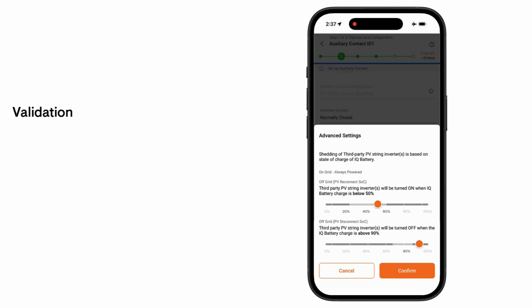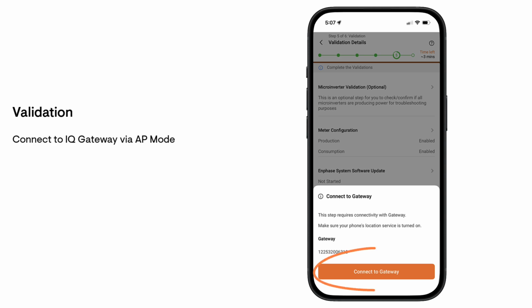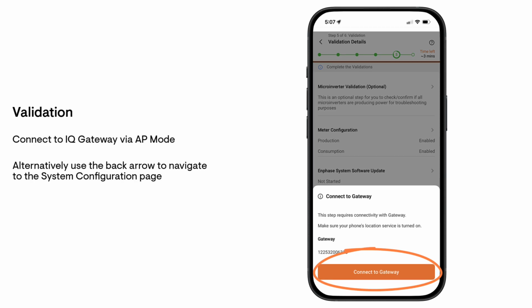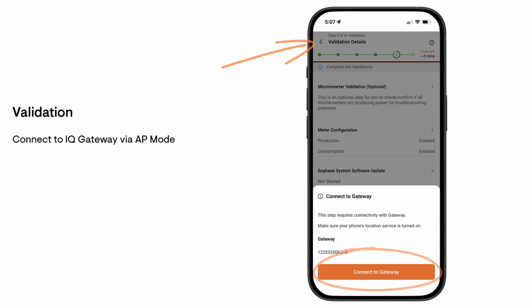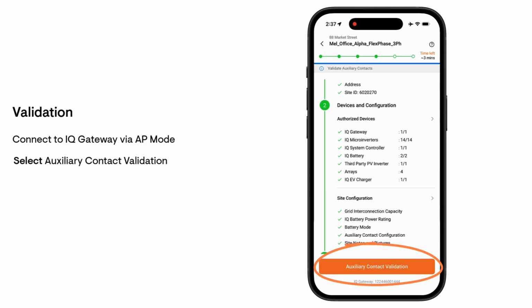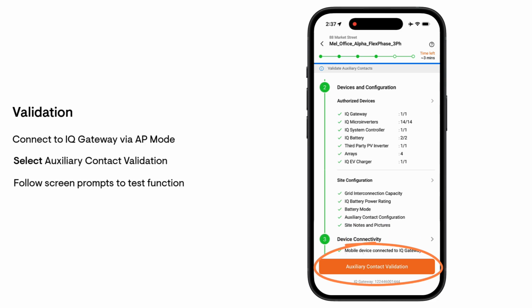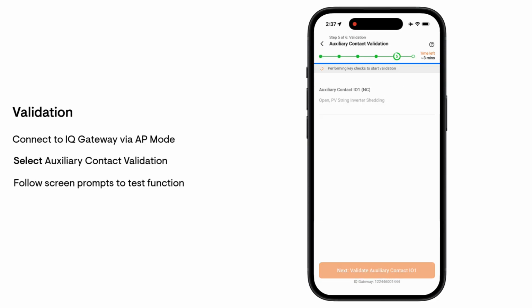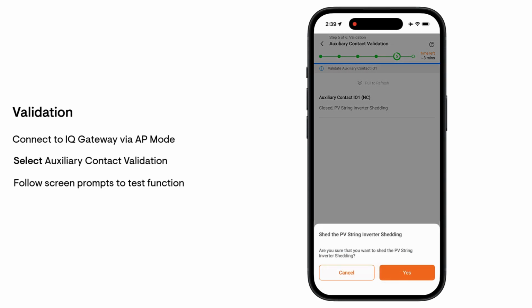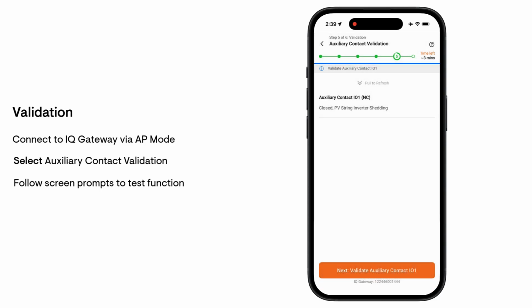Validation. Connect to the IQ gateway using AP mode. Note that the IQ gateway should already be connected to the home's internet connection via Wi-Fi or Ethernet. Alternatively, use the back arrow within the Installer app to navigate directly to the validation section of the system configuration page. Select Auxiliary Contact Validation and follow the on-screen instructions. The validation process automatically opens and closes the contactor to confirm correct operation and wiring. After successful testing, complete all post-commissioning checks.